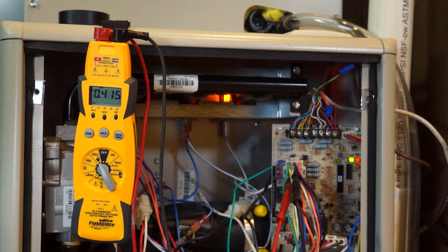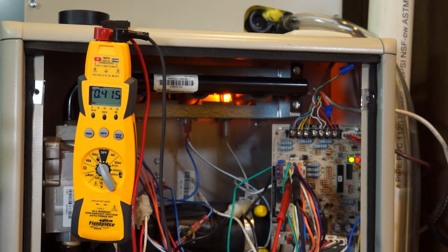There, the igniter is now starting to glow. You can already see our ignition process. So in a second here, you're going to hear that board click and that's when I want to focus on this meter up here and it's going to give you what voltage is getting out of the board to the gas valve. Remember it being a 24-volt load.